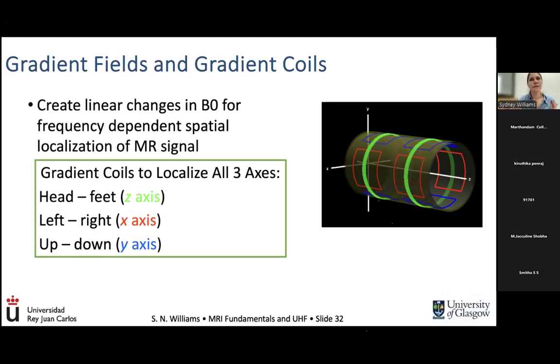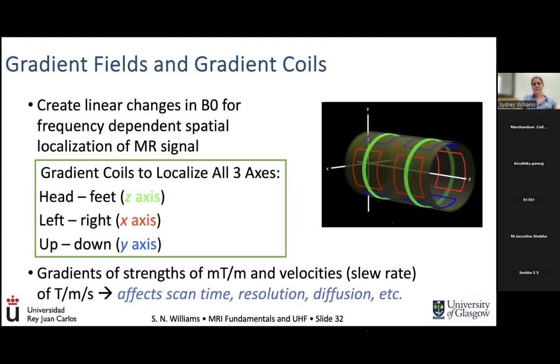Otherwise, if we were to receive the signal of the spinning protons as they precess, it would just be a mix and we couldn't map where the signal came from to the spatial location of the body. So gradients are hugely important. But gradients are also the part of the scanner that really gives you the imaging performance, because they have a certain strength of that linear shift that they can generate, normally in the order of millitesla per meter. And they can only go so fast, which is called their slew rate, in the order of Tesla per meter per second. So the quality of the gradients is going to have a huge effect on the ability to scan fast in MRI, to give you a good resolution. It also has a large role in certain types of applications, like the diffusion imaging I mentioned earlier, which shows you the diffusivity along white matter tracks, for example, in the brain.